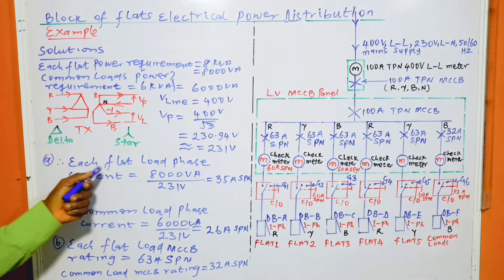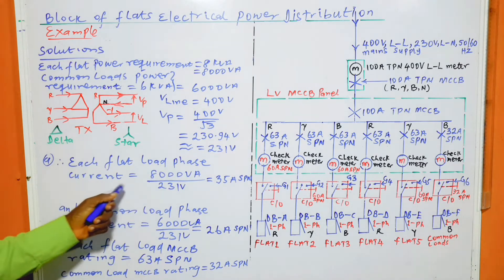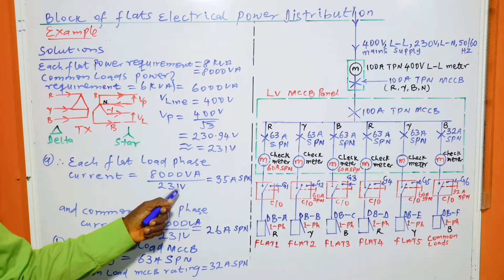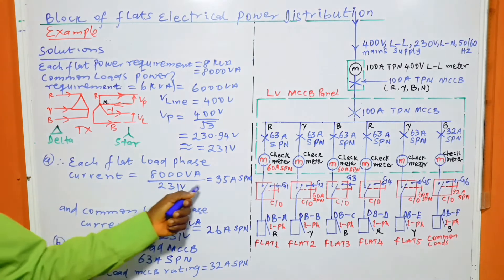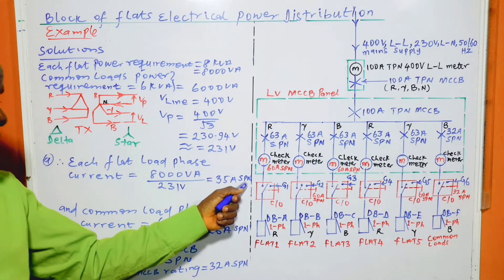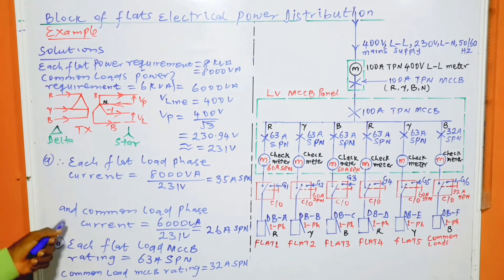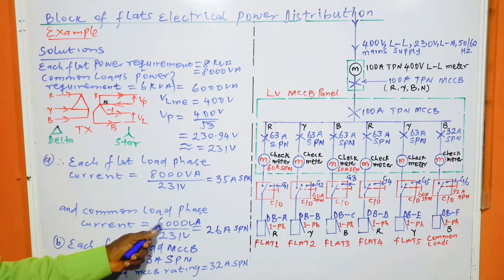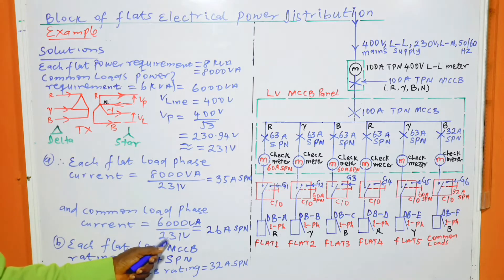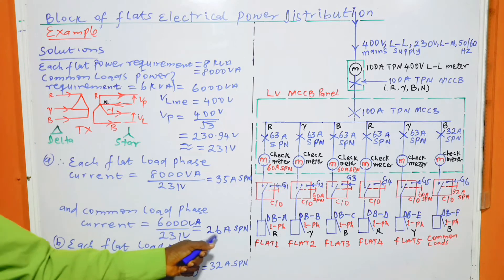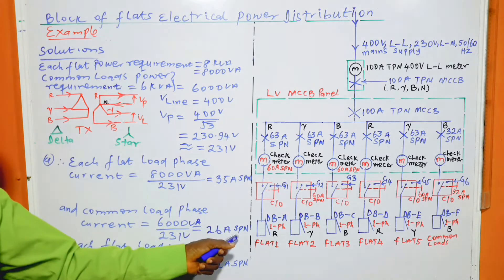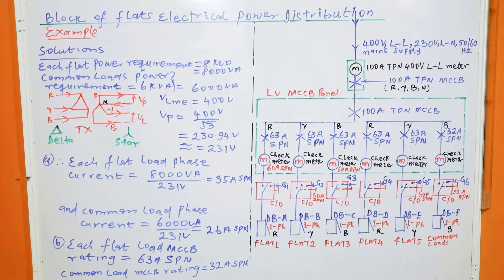Part A: each flat's load phase current is equal to 8,000 VA divided by 231 volts, which equals 35 amperes, single-phase with neutral. The common load phase current is equal to 6,000 VA divided by 231 volts, which equals 26 amperes, single-phase with neutral.